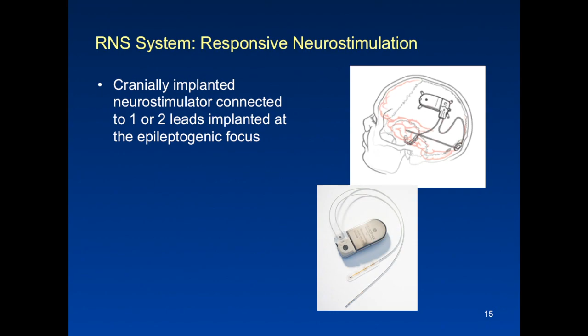The cranial implanted neurostimulator is connected to up to 2 leads. Those leads can take the form of a depth lead, which you see right here, or a subdural strip lead. Each lead contains 4 electrodes, and then the can is used as a reference. So there are basically 9 points of reference and 8 for stimulation. The physician decides whether strip leads or depth leads or a combination of the two are implanted depending on the seizure focus. The neurostimulator has 2 custom integrated circuits, the battery and a connector assembly.